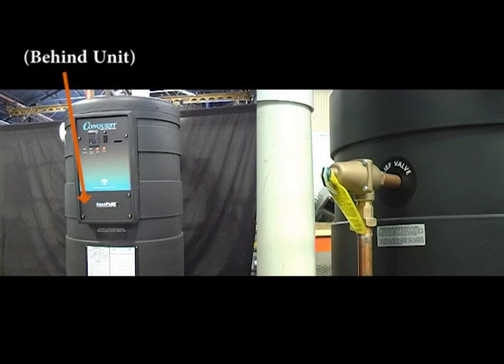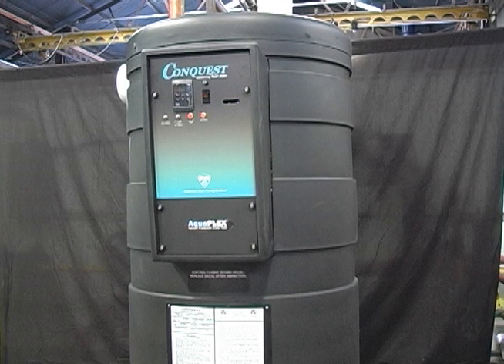Also ensure that the temperature and pressure relief valve is properly piped to a floor drain in accordance with local codes and with no valves or restrictions in the piping. The installation must be complete prior to performing initial startup, and the startup must be complete prior to placing the water heater into service. Starting the water heater without proper piping, combustion air, venting, or electrical systems can be dangerous and may void the product warranty.